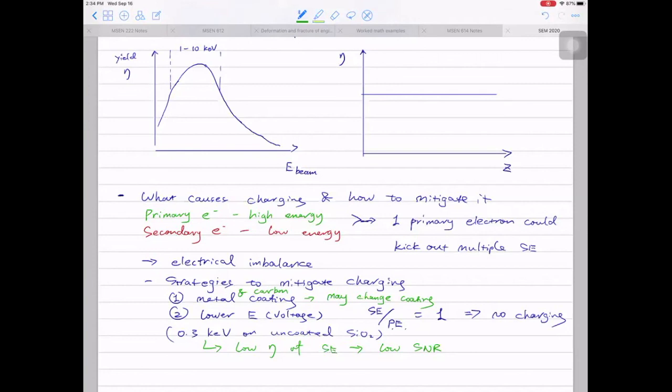If you're looking at a bulk sample with features hundreds of nanometers in size, coating is the way to go. If you're looking at something very, very small, using a lower voltage is the better approach. Towards the end of the course we'll introduce another technique — helium ion microscopy — as another way to mitigate charging issues.